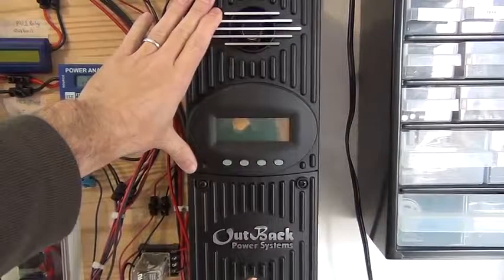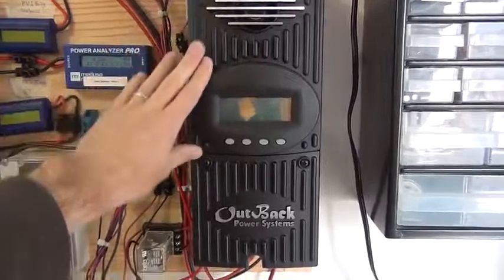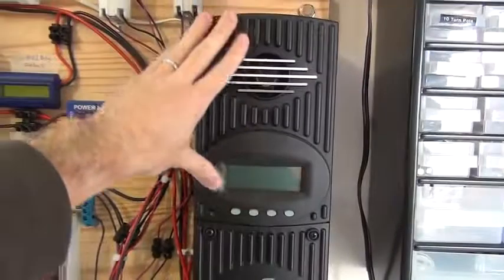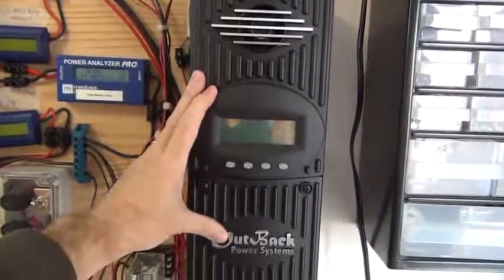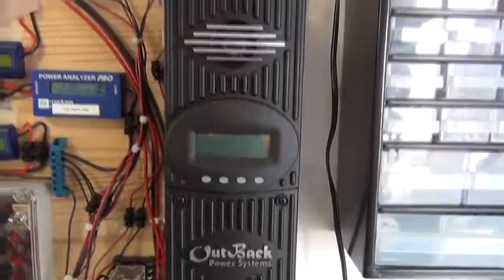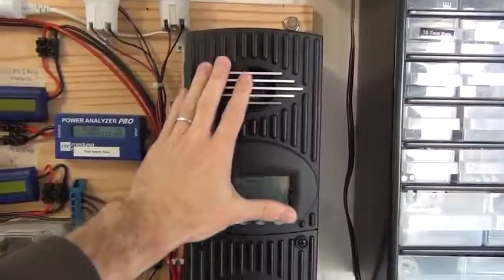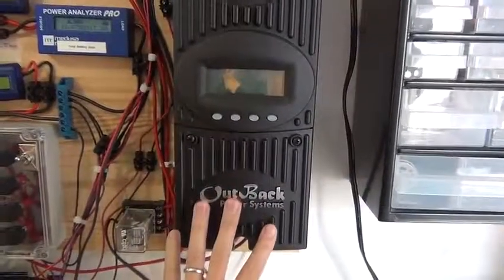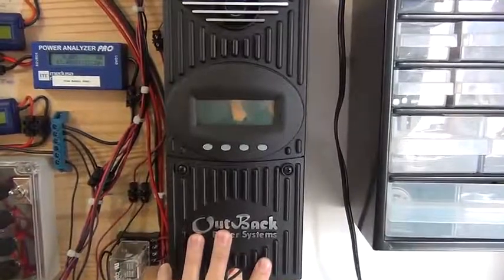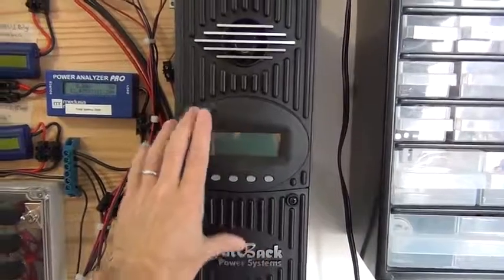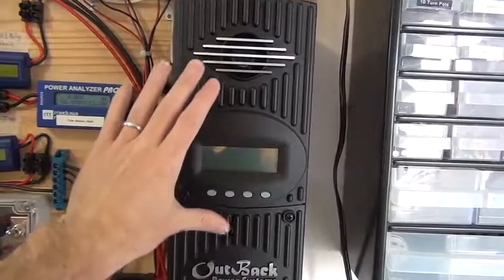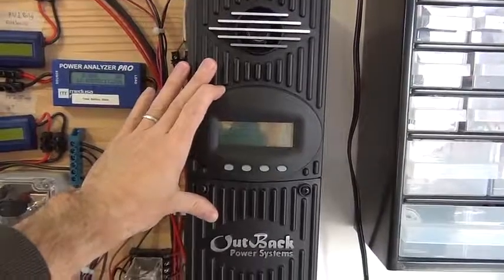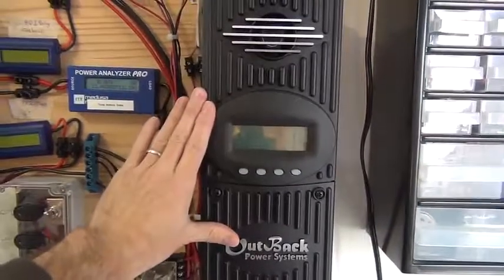This is an MPPT charge controller—a maximum power point tracking charge controller. This device is especially useful in off-grid systems as it takes power from the solar panels, does a DC to DC conversion so it's at the right voltage for your battery bank. This can't supply power directly to your house, which is why it's more useful in off-grid systems.